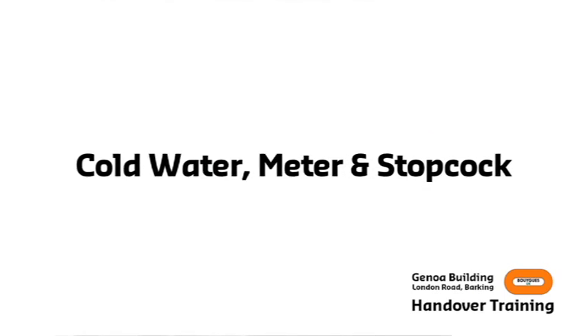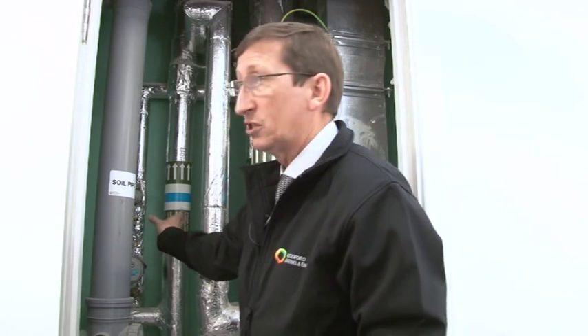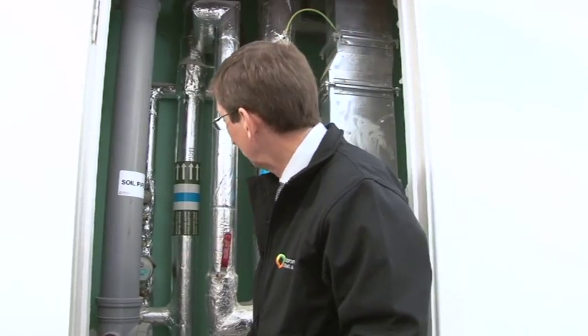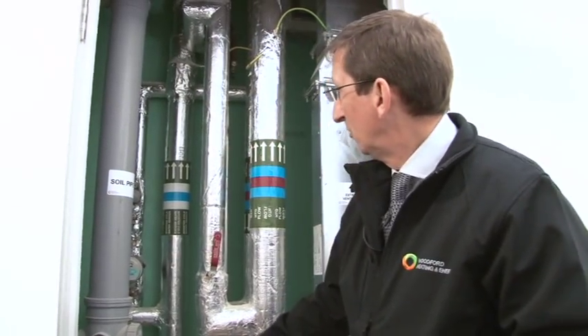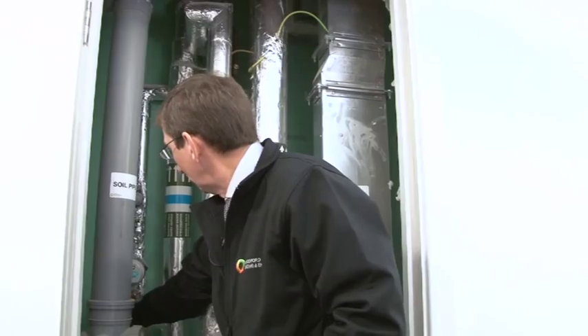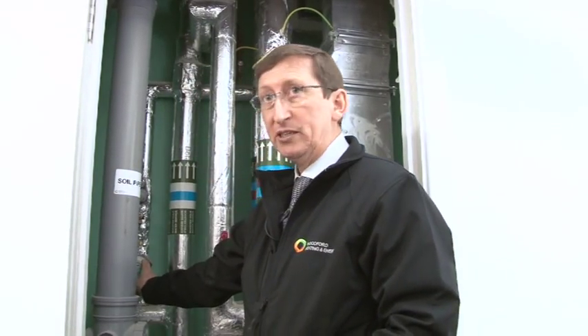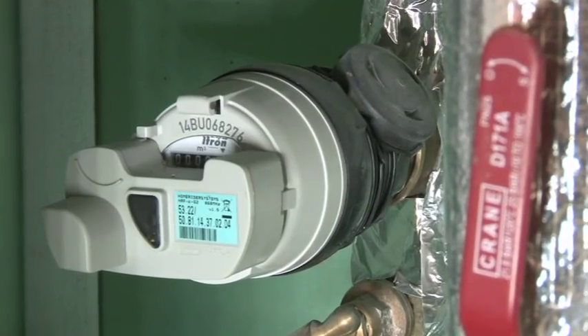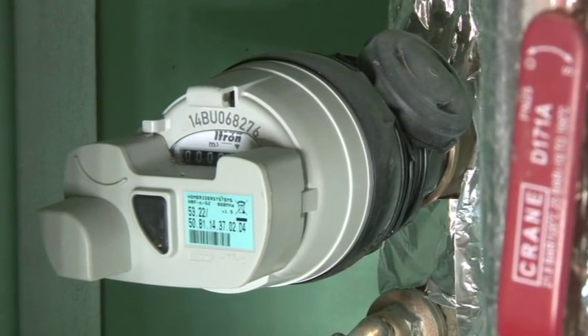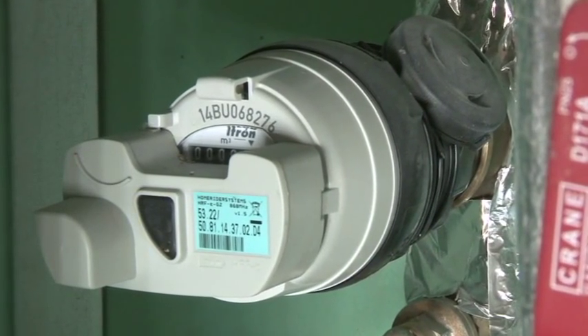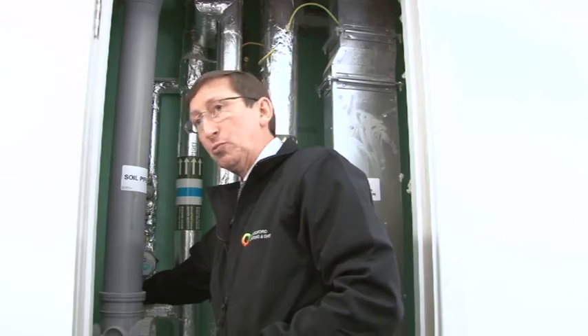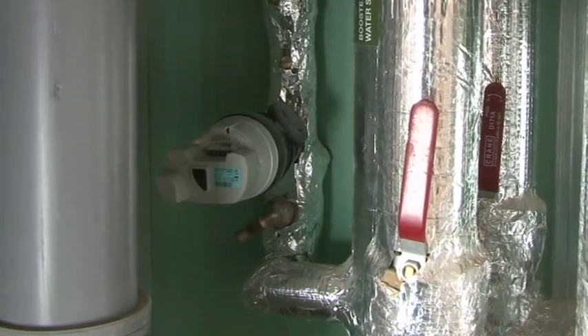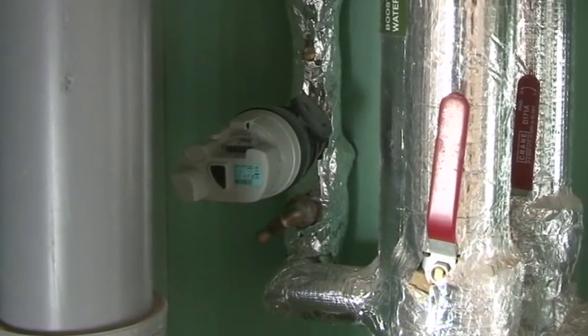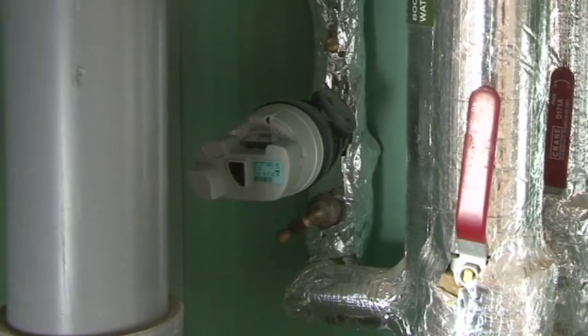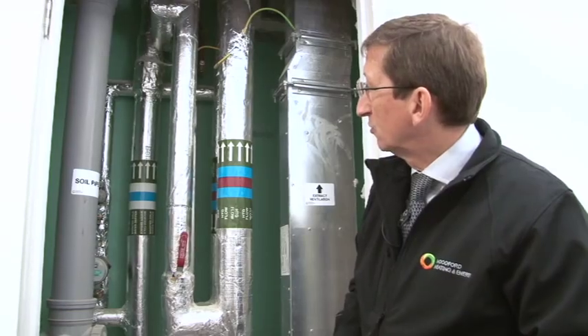At the back of the cupboard we have the boosted cold water. There's a cold water distribution around all the different flats coming from the main plant room and from the tank room, and you can see the take-off there and the water meter for the particular flat that's being fed off this cupboard. There's an individual water meter per flat. There's a stopcock below that to turn off the water supply into the residence, so that's another point of access to stop that external to the unit.